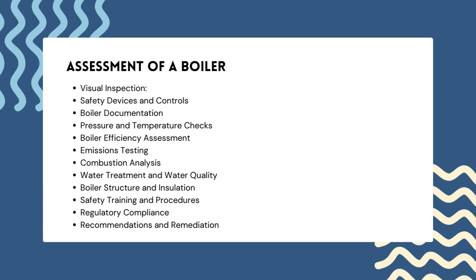Second, safety devices and controls: inspect pressure relief valves, water level controls and flame safeguard systems, ensuring all safety devices are in good working condition and have not been tampered with. Third, boiler documentation: review design specifications, operating manuals and maintenance records, and verify that the boiler has been properly maintained and serviced according to the manufacturer's recommendations.